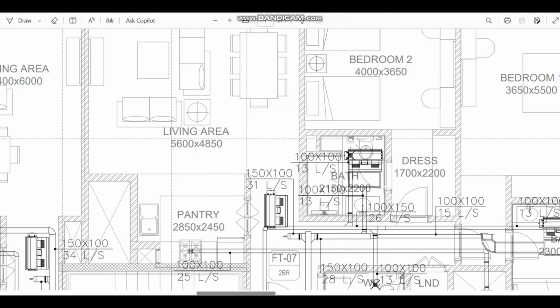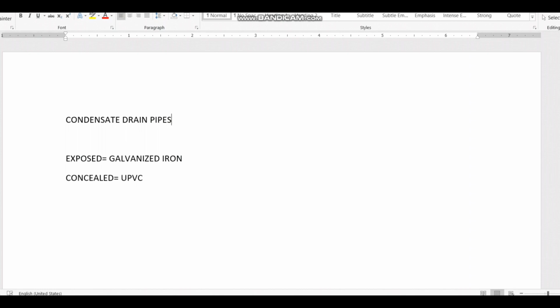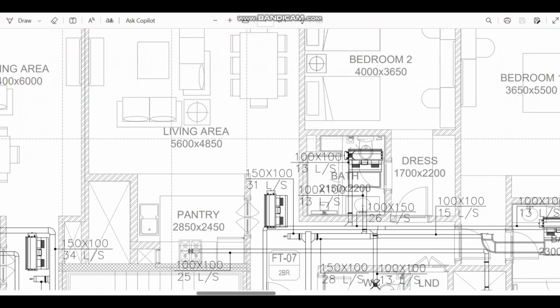The next point for the FCU we need to consider is the condensate drain pipe. So here we have to consider some key points. When it comes to condensate drain pipes, mostly in the Middle East, for the exposed condensate drainage pipe, we use galvanized iron with insulation. And when it comes to concealed, that means inside the wall and underground buried, we normally use UPVC with a high pressure rating. We are using this one.